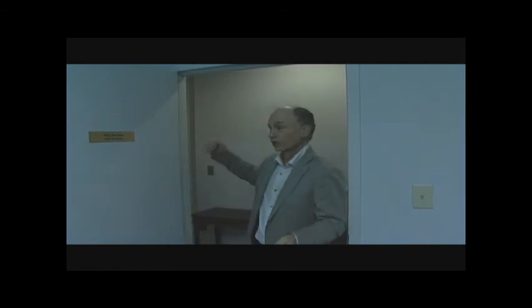Here we are inside — a tight view. Here's where the old opening was that George has now sealed up. You also see the open ceiling tile up to the attic. Air will move following a path of least resistance — if it's easier for the air to come down from the attic or from the outside, it will. That is the law of physics, specifically the second law of thermodynamics. Now, if you're in a room where supply air is coming out and the door is closed, the air can't get to the hallway — you unbalance the system. The solution our heat and air contractor used was to install a pass-through grill, simply an opening between the two rooms to balance the system. We need to look at this particularly in bedrooms in residential homes — very often, carpet will block the bottom of the door and prevent air from moving from the supply end to the return end.